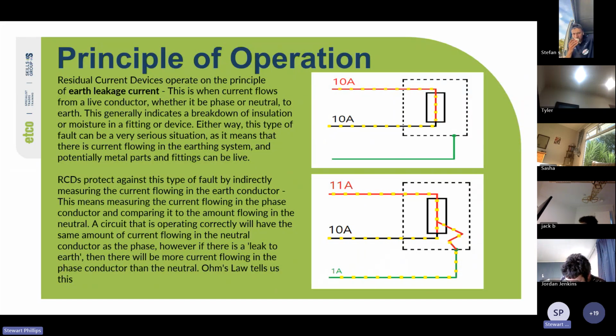The RCCBs protect against this type of fault by indirectly measuring the current flowing in the earth conductor. This means measuring the current flowing in the phase conductor and comparing it to the amount flowing in the neutral. So a circuit that is operating correctly will have the same amount of current flowing in the neutral conductor as the phase conductor. However, if there is a leak to earth, then there will be more current flowing in the phase conductor than the neutral. So Ohm's law tells us this.